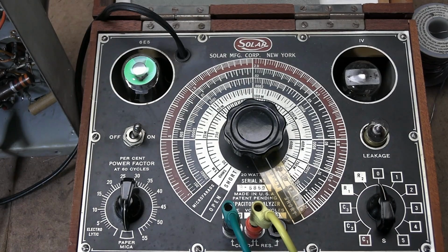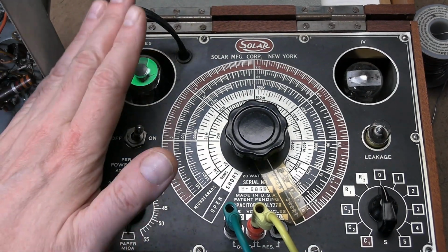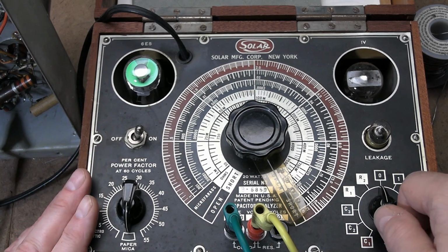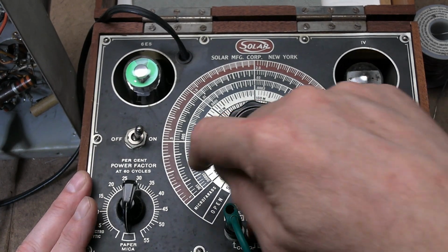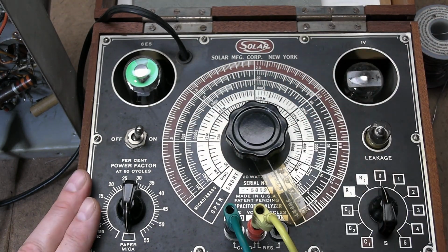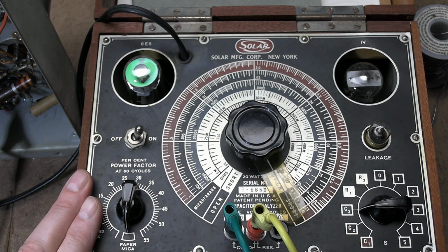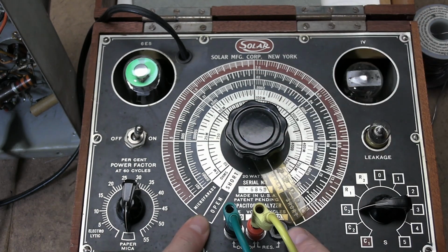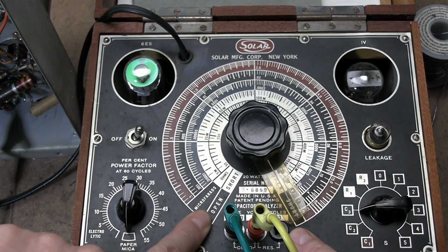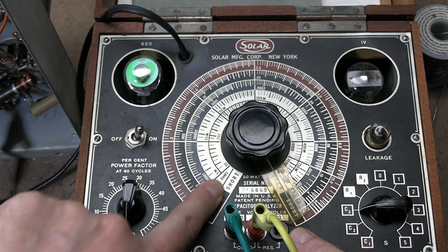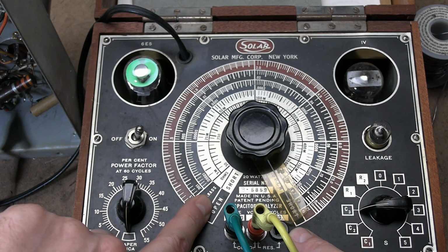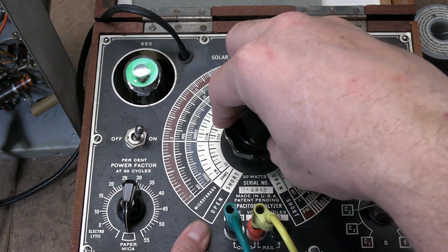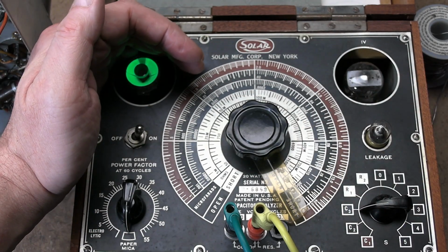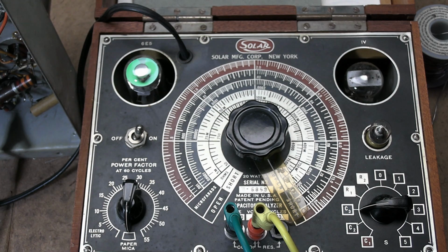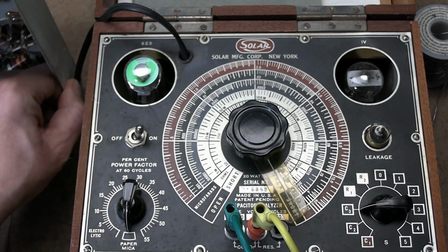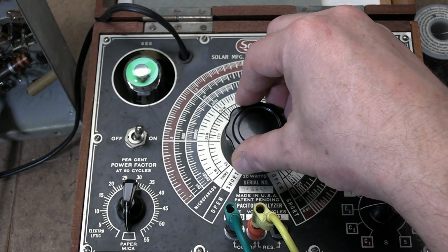Let's try checking the value of this cap. Sometimes you can if they're very leaky. This eye tube just won't react properly, but let's give it a shot. This is 5,000, so I think we want the smallest range, which would be C3. Notice these, when you go to one extreme or the other, there are labels on here: open. If it's an open capacitor, the eye will open when you're all the way to this side. This side has short on it, and when I'm at short, notice the eye is partially opened, meaning it's a partially shorted cap, meaning it's very leaky.